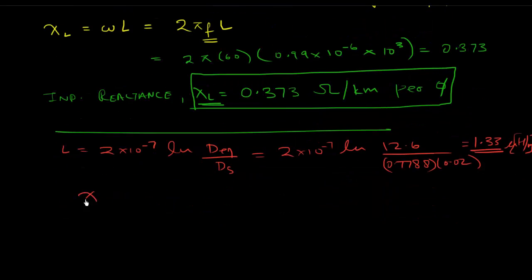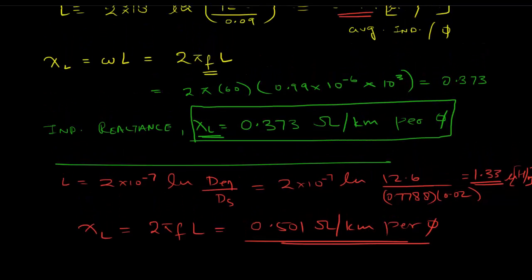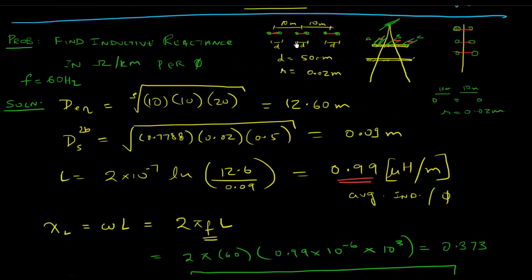You see, this is 1.33, this is 0.99 - the difference, how much lower this is. This would obviously have a direct impact on your XL value because your XL now becomes 2πfL, and you plug in this for L, and your value comes out to be 0.501 ohms per kilometer per phase.